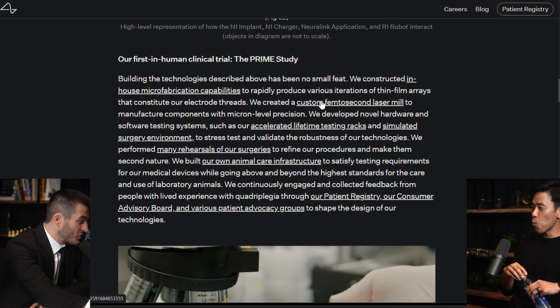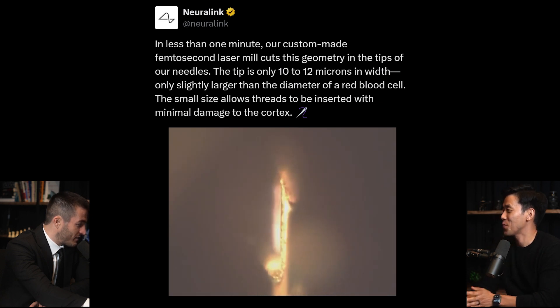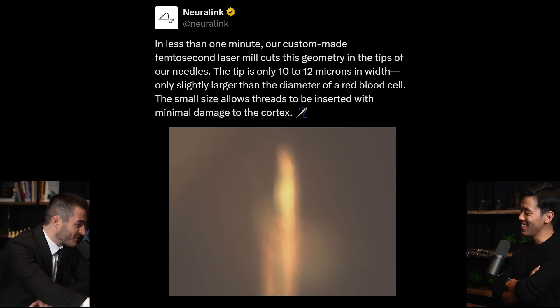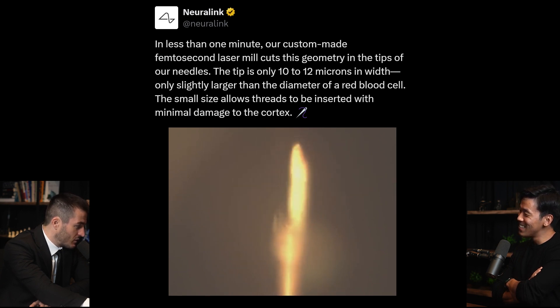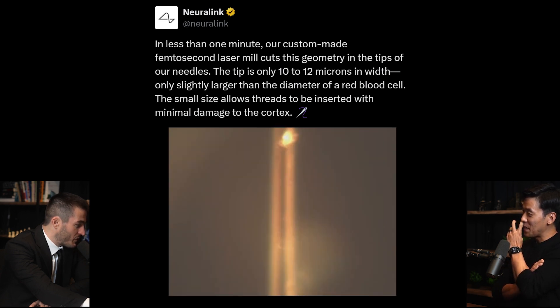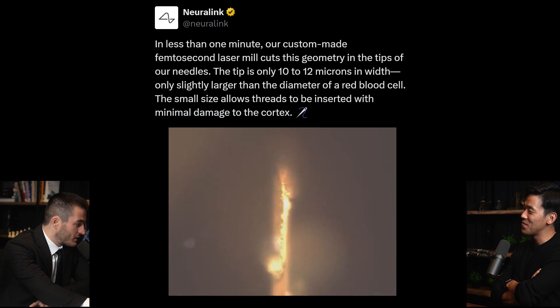We created a custom femtosecond laser mill to manufacture components with micron-level precision. In less than one minute, our custom-made femtosecond laser mill cuts this geometry in the tips of our needles. We're looking at this weirdly shaped needle — the tip is only 10 to 12 microns in width, only slightly larger than the diameter of a red blood cell.